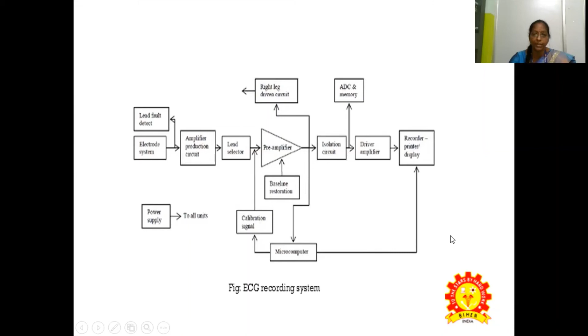A preamplifier: its function is to eliminate noise such as other biopotentials or various electromagnetic interference resulting from nearby communication links. Generally, a differential amplifier with high input impedance and high CMRR is used. Calibration: the function of this block is to calibrate the display or the recorder for a predetermined amplitude. A sine wave of 1 millivolt is generally used for this purpose.